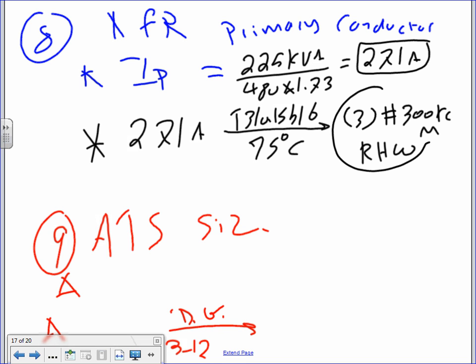RHW. So should we multiply it by 1.25 again? We already multiplied. If you look at how we got the transformer, it's already oversized. In the past I used to multiply by 1.25, but there's no need for multiplying it by 1.25. Did you say 300? Did we get a second on that? Yeah. Okay. A lot of things are going to depend on it. Okay, so that's number 8.